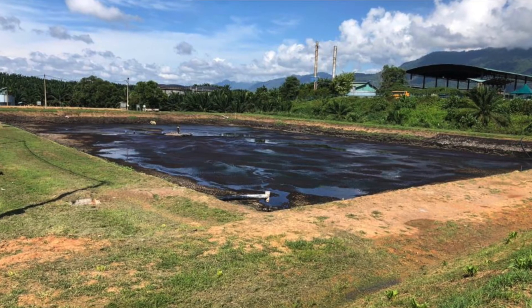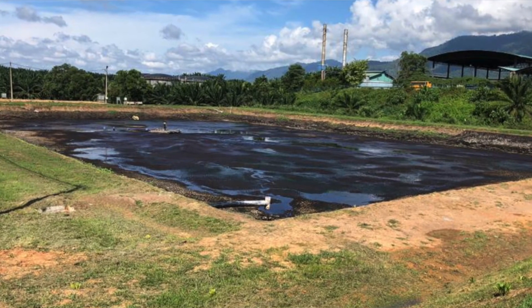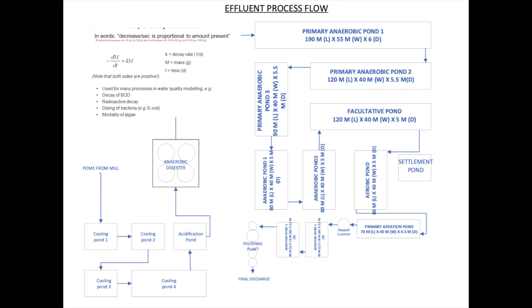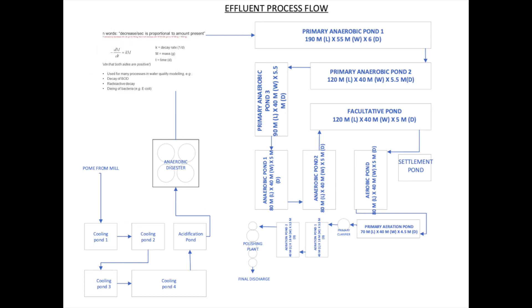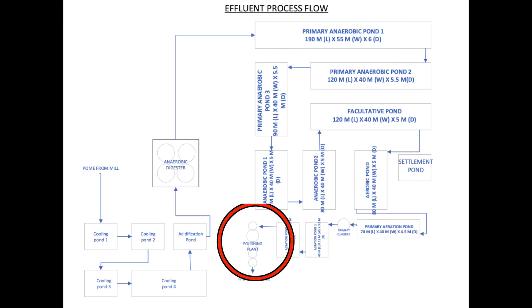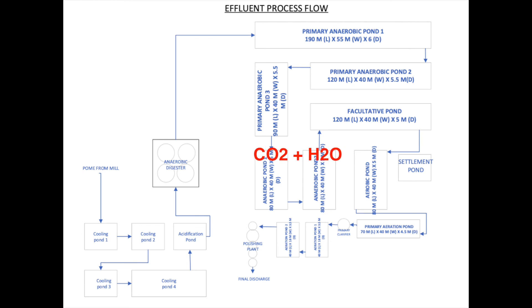With appropriate prior desludging and then application of our bioaugmentation technology, we confidently feel that we can achieve BOD 20 well before the POME reaches the primary aeration pond. Based on the enhanced decay coefficient using our advanced microbial treatment, we feel we can achieve BOD 20 by perhaps 0.4, 0.5, or 0.6. Given the pending upgrade to a 90-tonne mill, the primary aeration pond and the polishing plant are a good insurance to have. After treatment with our customised microbials, there will be less odour because indigenous bacteria produce ammonia and hydrogen sulphide, while our customised bacteria produce carbon dioxide and water.